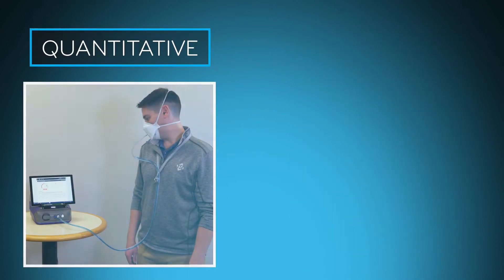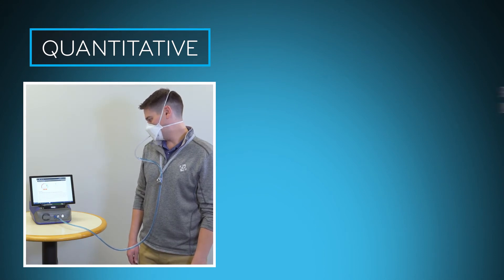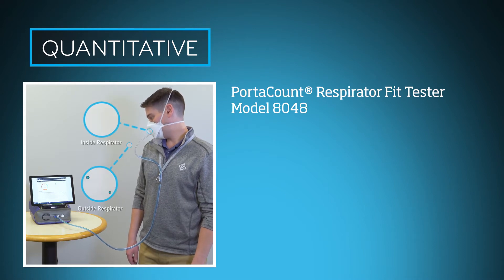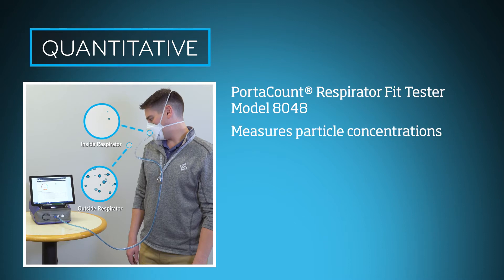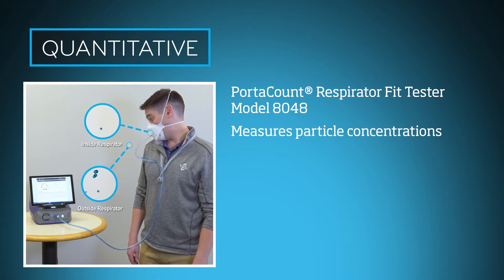Quantitative fit testing is an objective testing method, meaning that the test returns data on the measurements taken. The quantitative instrument shown in this video — the PortaCount fit tester model 8048 — takes measurements of the particle concentrations both within and outside of the respirator.